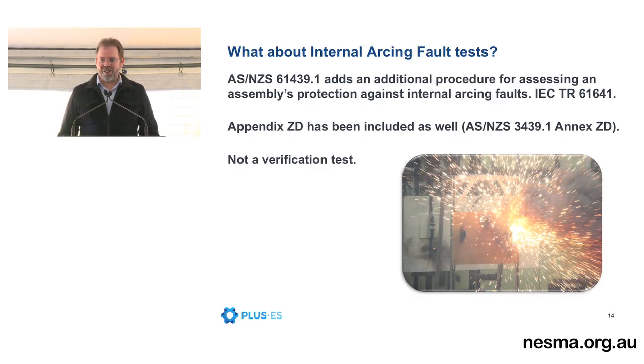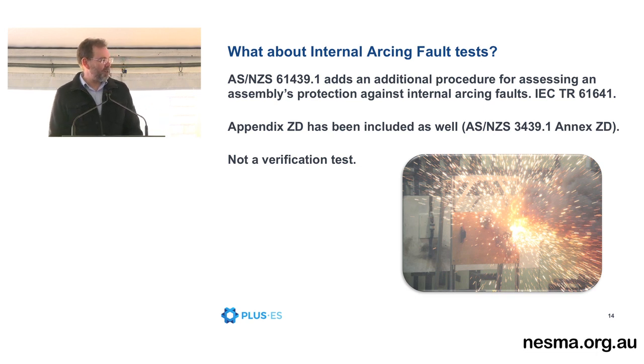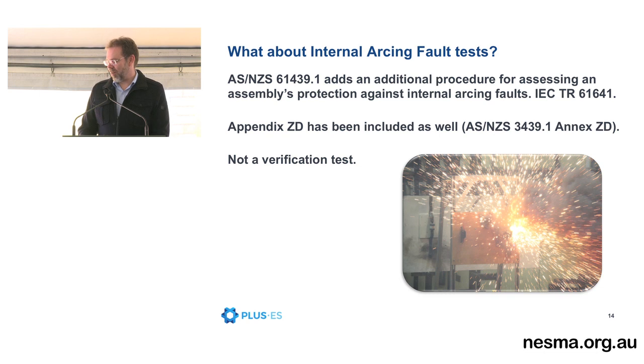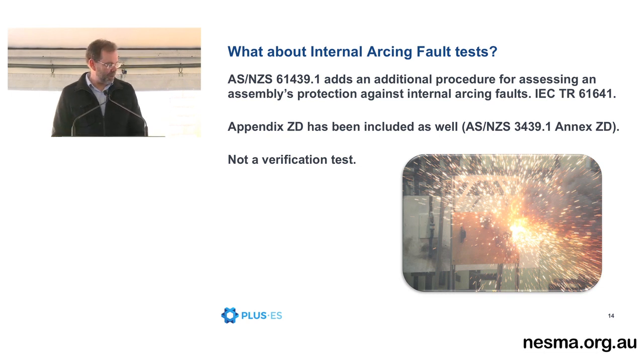I haven't mentioned internal arc fault tests. What we're actually going to see after my presentation is some arc fault testing, but it's not mentioned in that table that I presented, and the reason is that it's still not a verification test. So you can get a fully verified switchboard assembly, and it won't have, or doesn't need to have, arc fault testing in it. There is additional testing in the appendix.